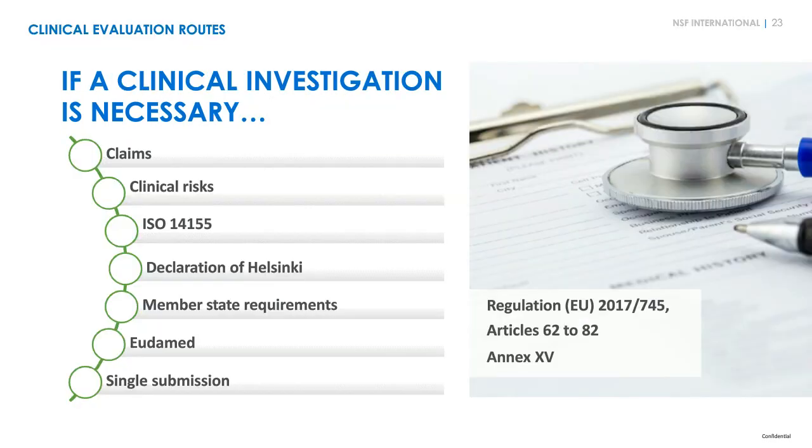If sufficient clinical data for the device under evaluation is not available and equivalence cannot be claimed, a clinical investigation will be necessary. To perform a clinical investigation, keep in mind that claims and clinical risks of the device should be taken into account when preparing the study protocol. In addition, not only the regulation, but also standard ISO 14155, the Declaration of Helsinki, and specific requirements of the member states of the EU have to be followed.